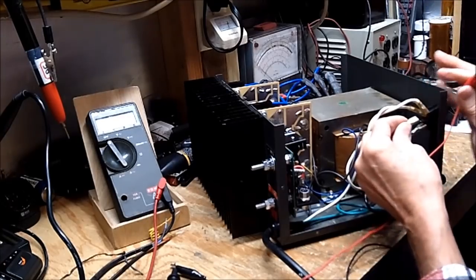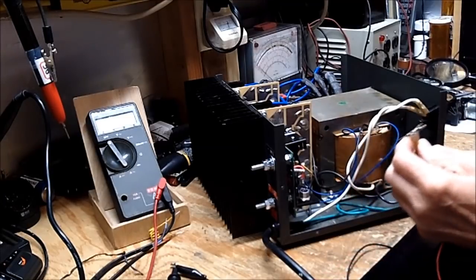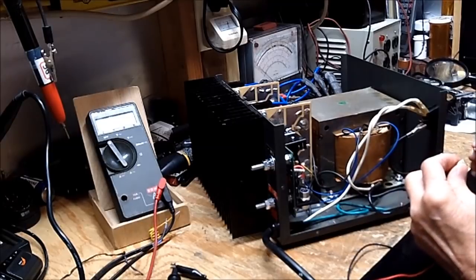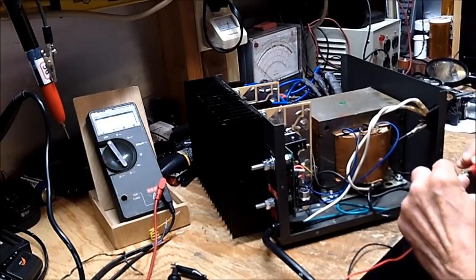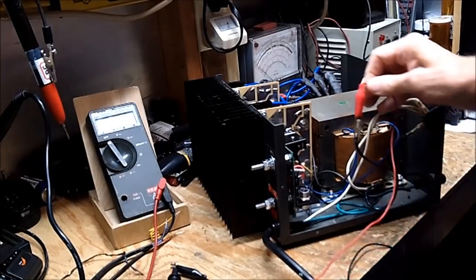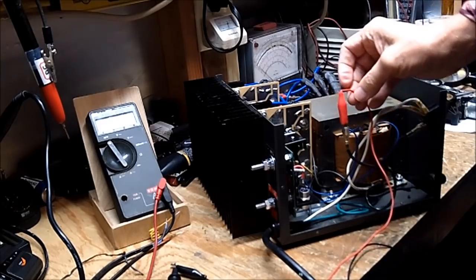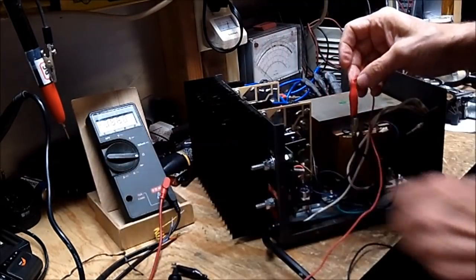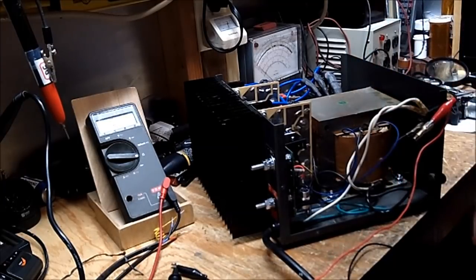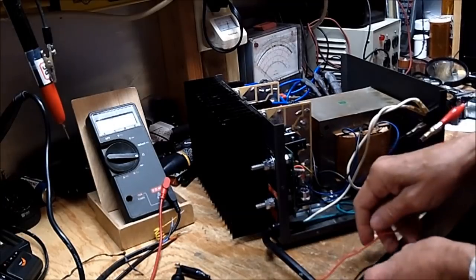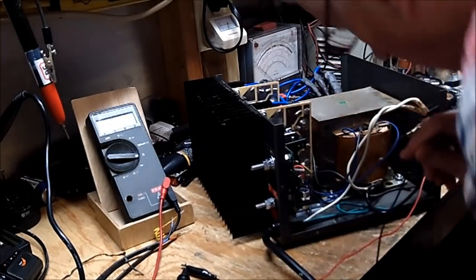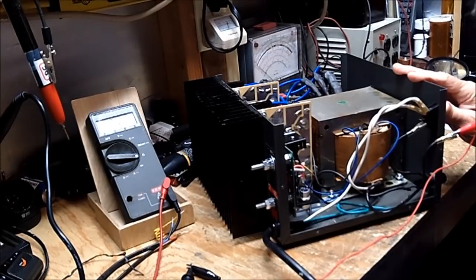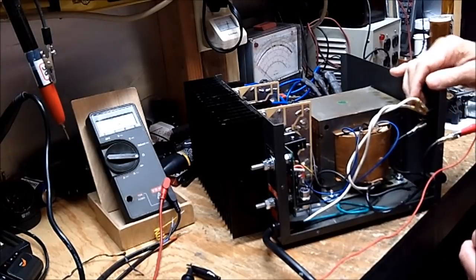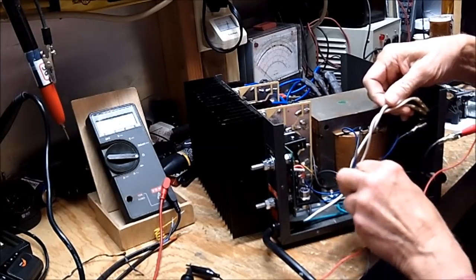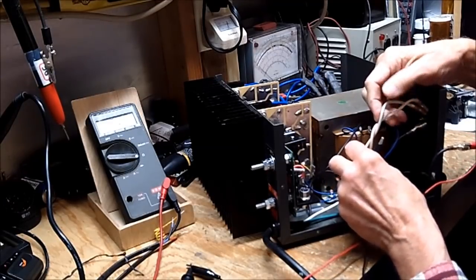Well, let's test this. Alright, this is the hot wire, this is the hot wire for the power transformer. Let's see if I can get my... alright, so we can see that. Alright, I got my ohm meter in there, let me put it on ohms here so it works better if I turn it on. Alright, so we've got our ohm meter on the hot side winding of the power transformer. Well, the best way to do that is let's just go right on the transformer itself so we don't confuse ourselves.